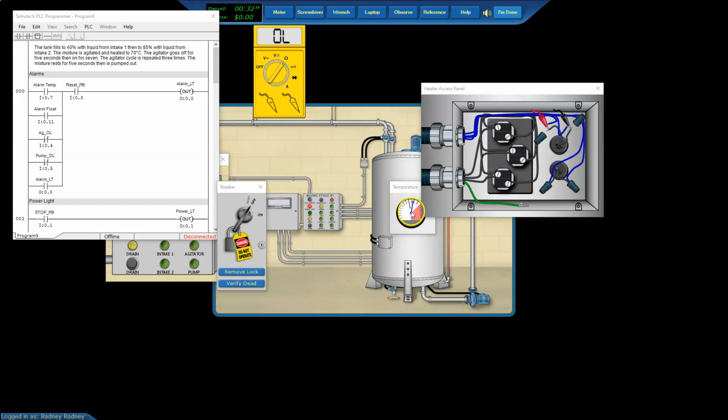So I'm going to wait a few minutes. I'm going to pause the video until we get there. But you can see that this switch is saying it is open right now. And all right, so you can readily see we're below 70 and the status of our temperature switch sensor has not changed. So we were right. It should have closed at 70 and above, and it didn't. And of course, if it closes at 70, it's not going to get above because at that point the heat would go off. So we have a potential for a bad temperature switch.